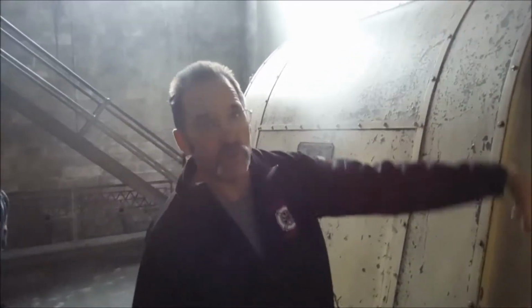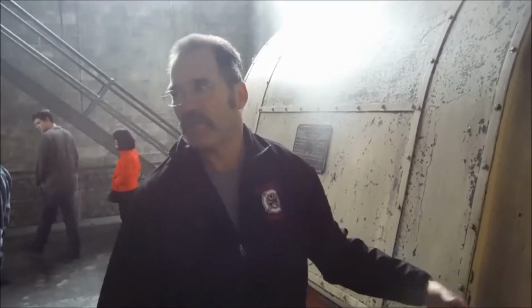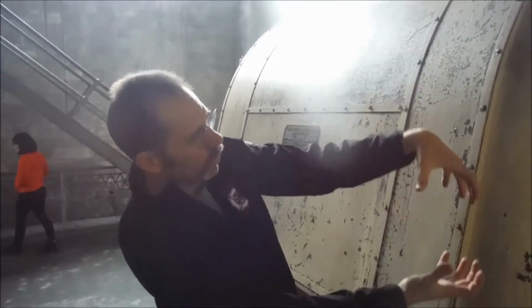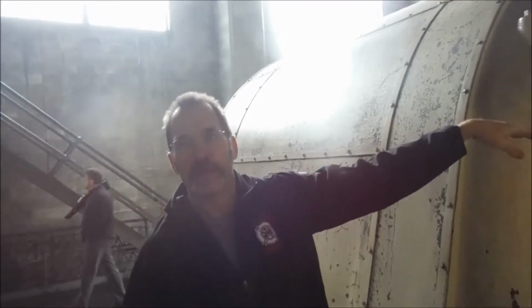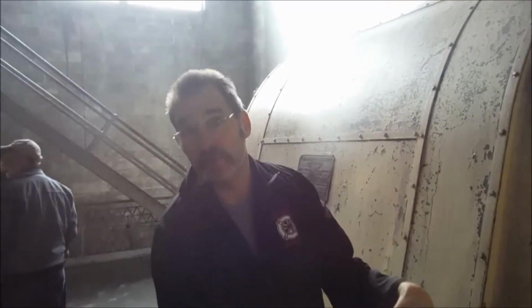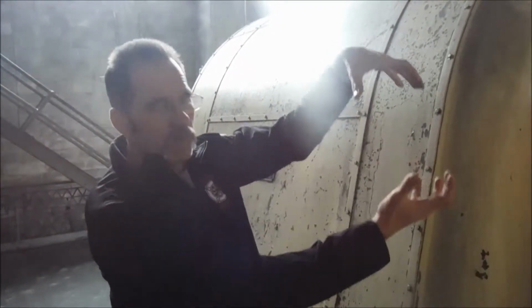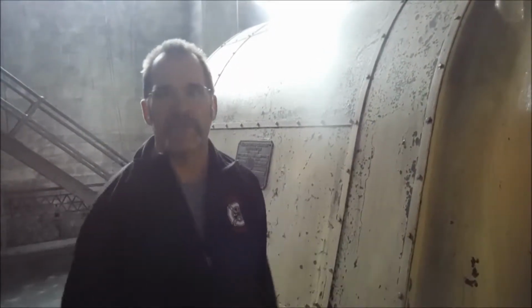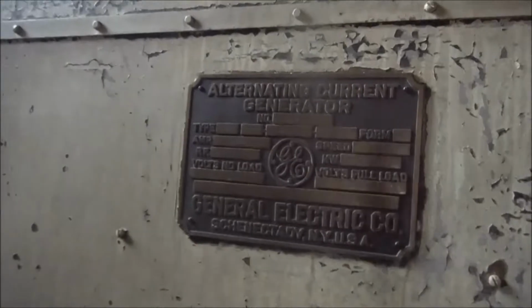And then every 6 months you'd pull that cap and measure down to the shaft with the turbine stopped, no oil in it, right? And so if the shaft was getting lower in relation to that flat spot, that would tell you that your bearing was wearing. Right. So that's how you'd monitor bearing wear, and if that shaft moved vertically more than X thousandths of an inch, like 3 or 4 thousandths of an inch, the bearing had to be replaced. And I assume it's a similar deal.